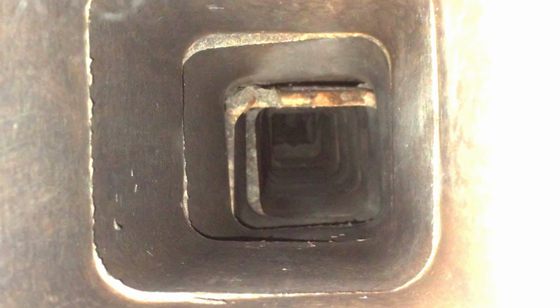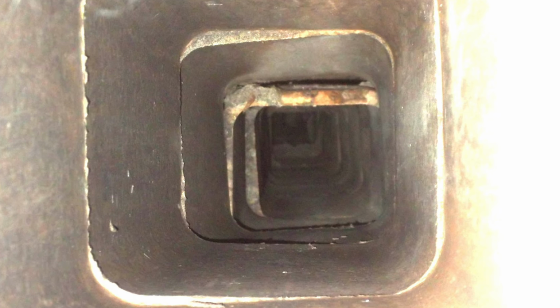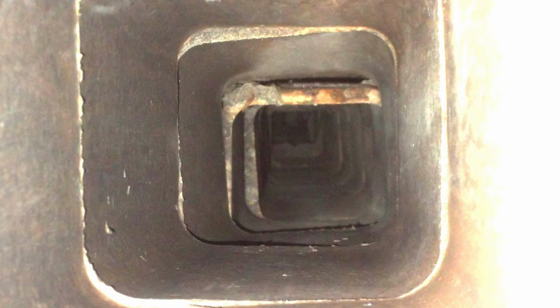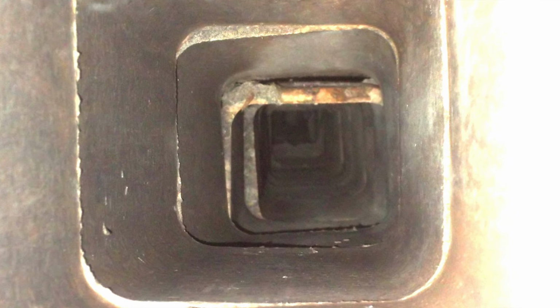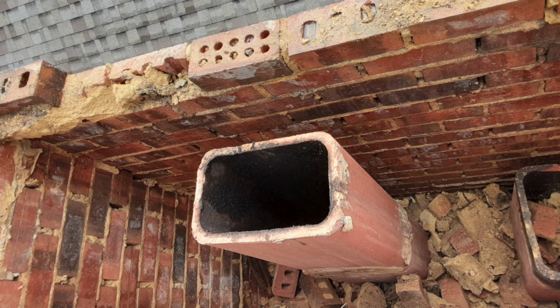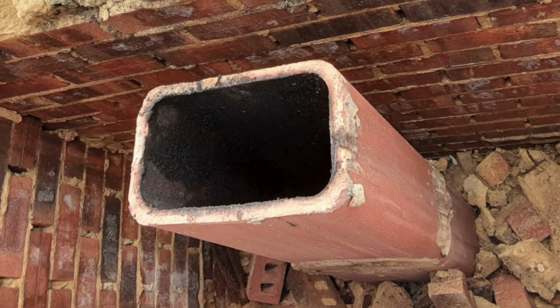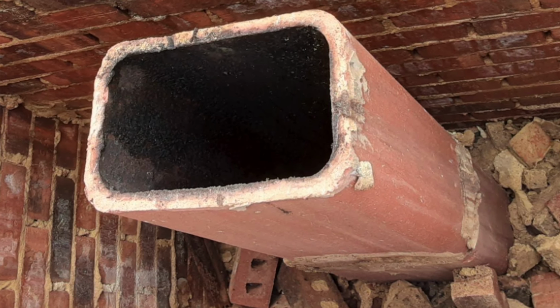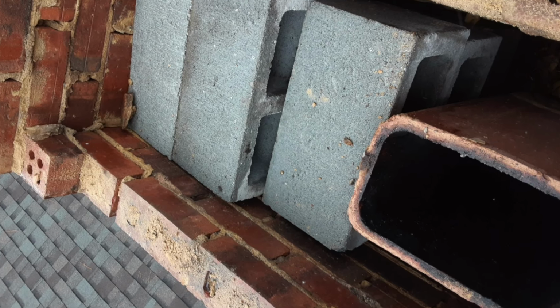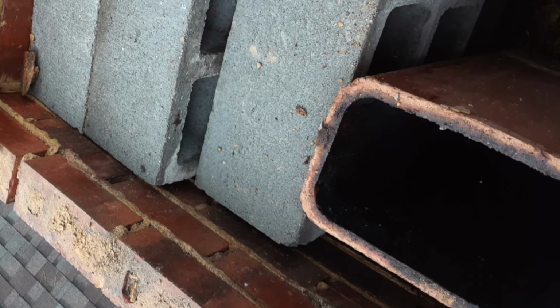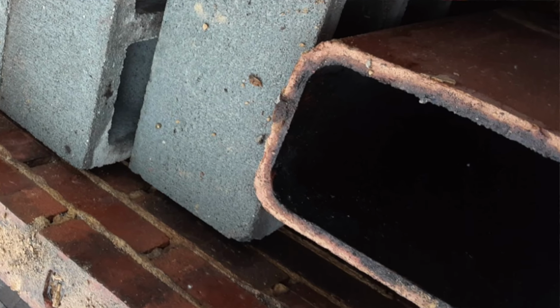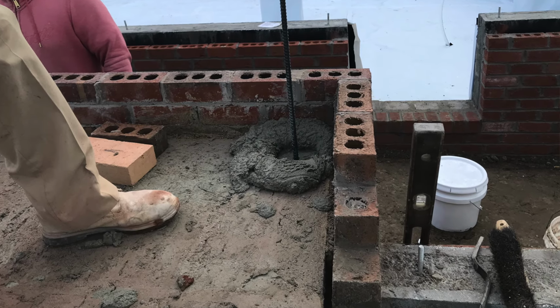There's long-standing confusion in the building industry regarding the amount of space required around a flue liner. NFPA 211 references a clearance range of 1/2 inch to 4 inches between the liner and the chimney wall, which has left many builders uncertain about the correct dimension. The reason for this variation is not actually about draft or safety. It stems from differences in seismic requirements.